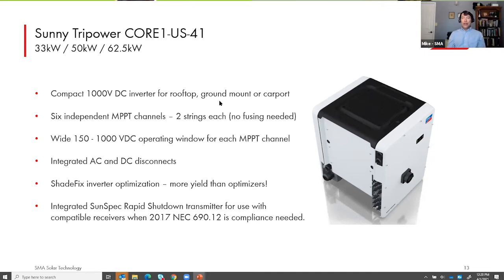The inverters, the change from the US-40 to the -41 model might seem a small number change. It brought in the 33 and the 62.5 kilowatt power classes into the Core 1 line, but also introduced built into the inverter a SunSpec certified rapid shutdown transmitter that makes compliance with all of the requirements of 2017 or 2020 NEC 690.12 very, very straightforward. We'll show the other piece of the compliance puzzle on the next slide, the SunSpec receivers, but the transmitter built into the inverter makes it very simple for compliance.